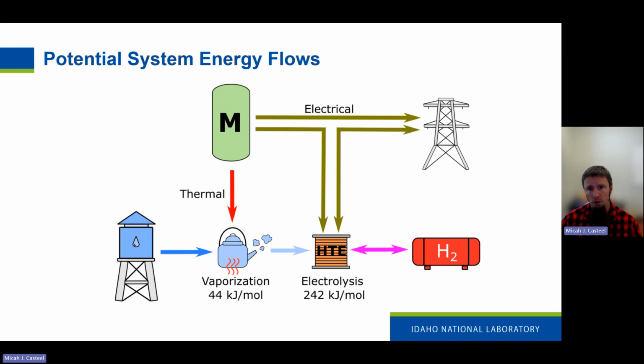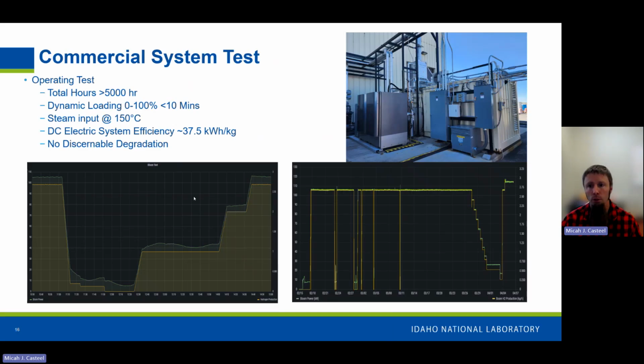In terms of testing commercial systems, at this point we've been testing a Bloom Energy commercial system for a little over 5,000 hours—closer to 6,000 hours now. It's been similarly very boring, in fact. You can see degradation is more or less non-existent. The system's been operating almost identically at 37.5 kilowatt-hours per kilogram DC input for the life of the plant.